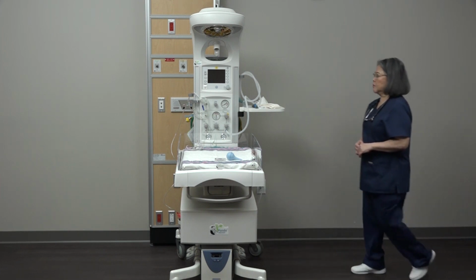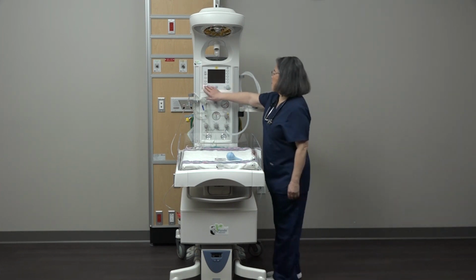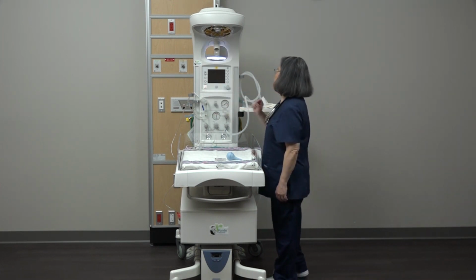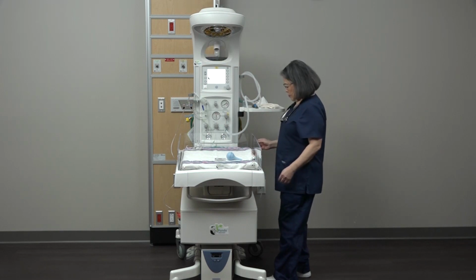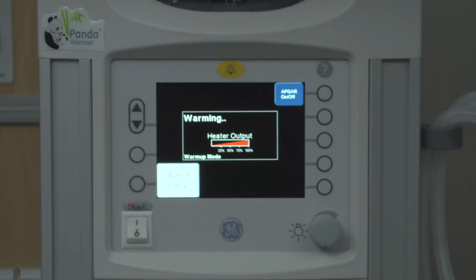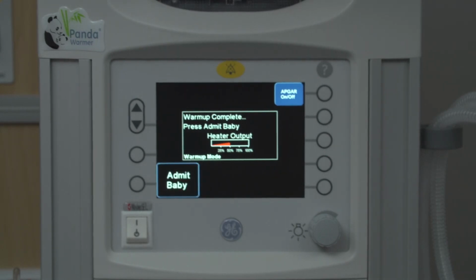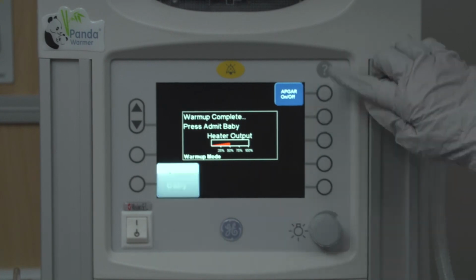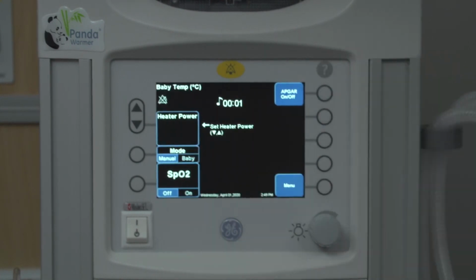Let's cover a few safety tips to keep in mind when operating the warmer. Always preheat your warmer, so it's ready to go when your patient arrives. The warmer has a warm-up mode that will operate at 100% power for 7 minutes, then automatically reduce to 50%. There are no alarms during warm-up, so the baby should not be placed in the warmer until after warm-up mode is complete, or you've hit Admit Baby or APGAR on.